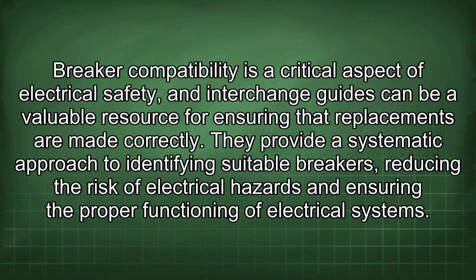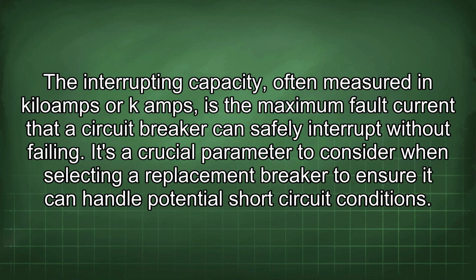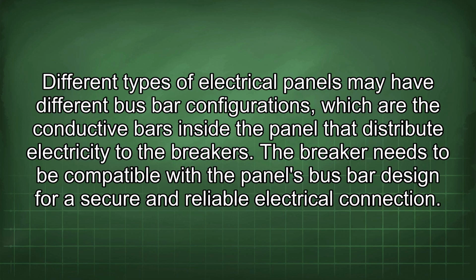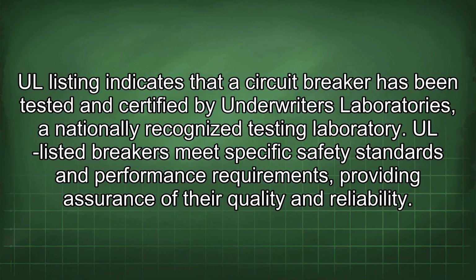The interrupting capacity, often measured in kiloamps or k-amps, is the maximum fault current that a circuit breaker can safely interrupt without failing. It's a crucial parameter to consider when selecting a replacement breaker to ensure it can handle potential short-circuit conditions. Different types of electrical panels may have different busbar configurations, which are the conductive bars inside the panel that distribute electricity to the breakers. The breaker needs to be compatible with the panel's busbar design for a secure and reliable electrical connection. UL listing indicates that a circuit breaker has been tested and certified by Underwriters Laboratories, a nationally recognized testing laboratory. UL-listed breakers meet specific safety standards and performance requirements, providing assurance of their quality and reliability.